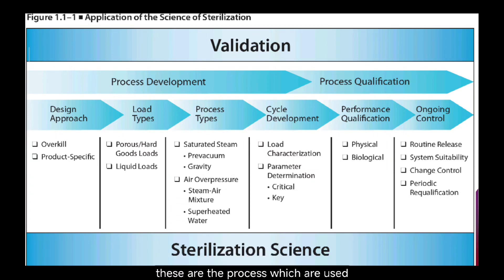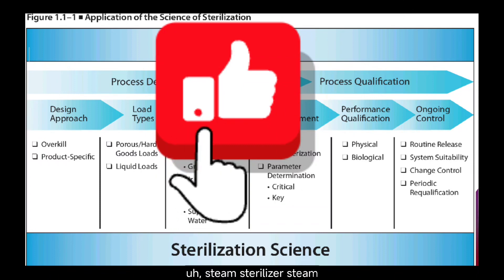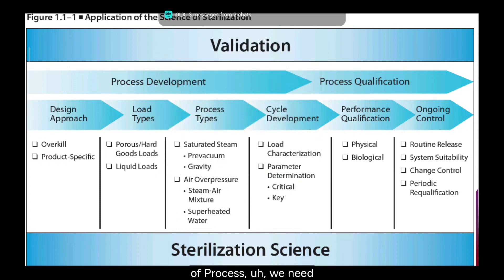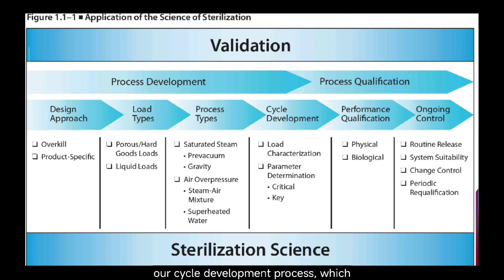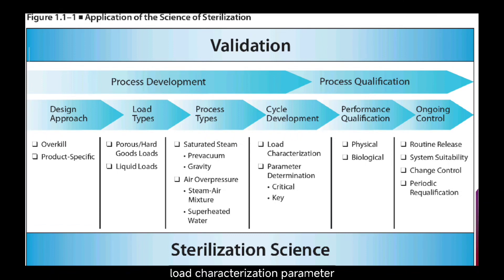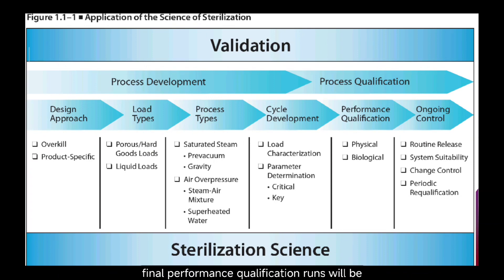These are the processes used for steam sterilizer qualification. Saturated steam and air overpressure cycles are used for qualification of steam sterilizers. After selection of the process, we initiate the cycle development process, which includes load characterization, parameter determination, and critical and key parameter determination.